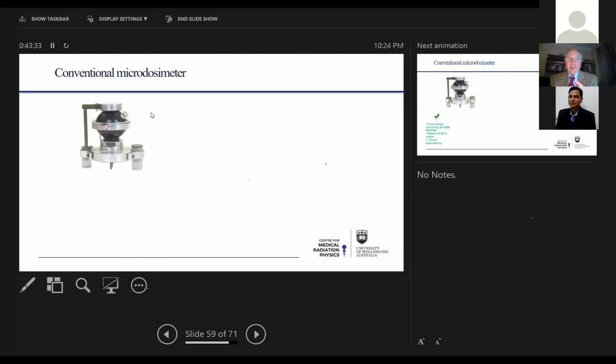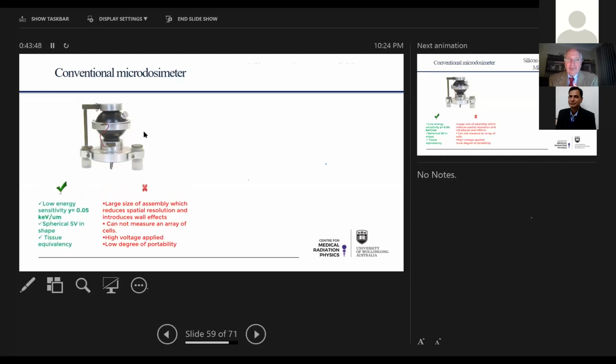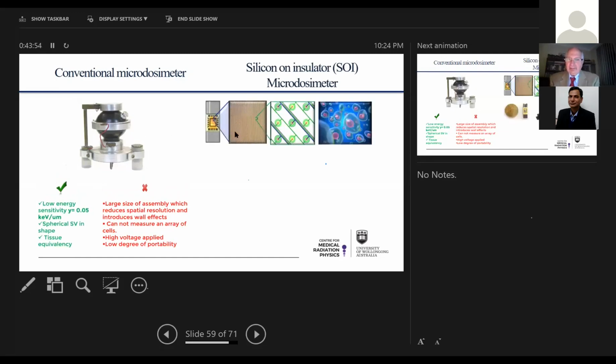People used to use microdosimeters like the tissue equivalent proportional counter. However, with such microdosimeters you can't do anything in stereotactic, proton therapy or heavy ion therapy. So we developed a silicon chip based on 1,000 silicon cells, modeling biological cells, micron-sized spherical and cylindrical diodes. The advantage of this detector is that you're modeling a group of cells simultaneously.